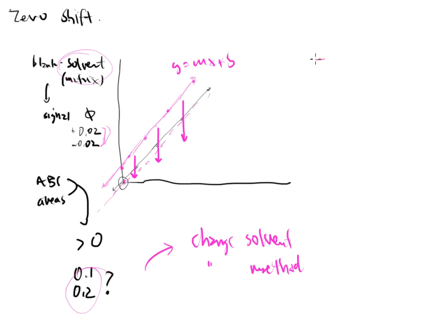In the software of many of the instruments, you're going to see a zero shift option. And you can check that box in the software system, and it will take this calibration curve and it will shift it down to make it go through the 0.00. So what's the big deal? Why am I going on and on about this?